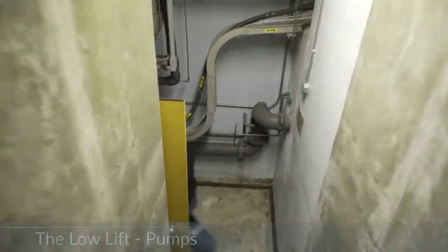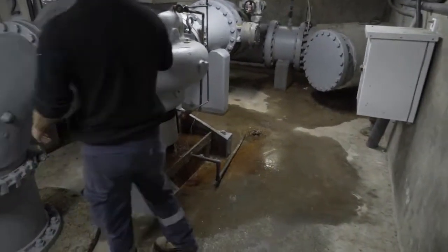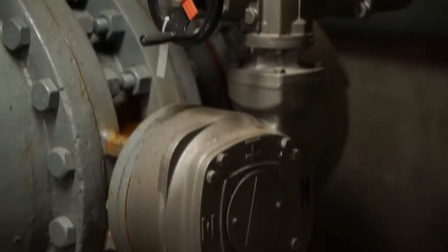The low lifts are single stage, whereas the high lifts are 2-stage to get the higher pressure rise to service the distribution system. A 2-stage pump is essentially 2 pumps in series built into the same casing. In this building, you can see the low lift pumps. We'll see the high lift pumps later on. Pressure at the pump suction has to be high enough to avoid boiling the water inside the pump when the velocities go up.